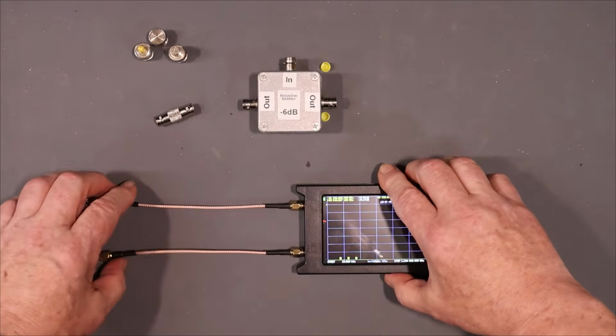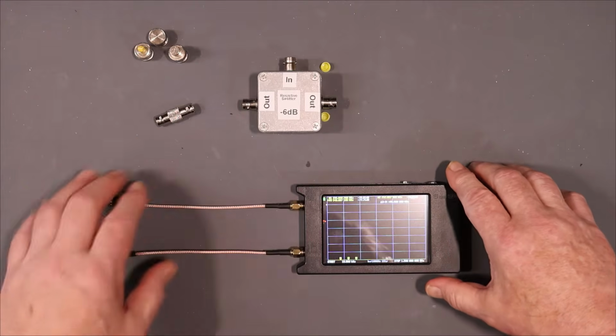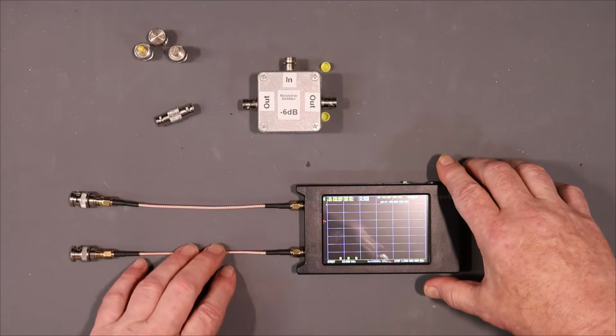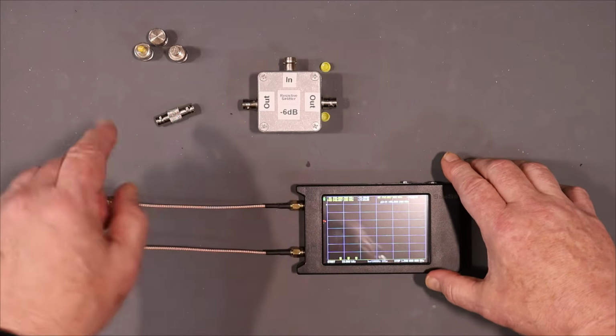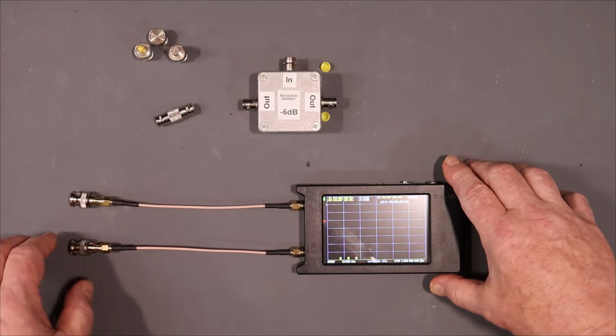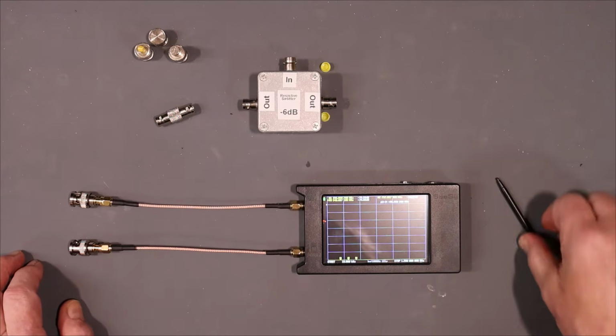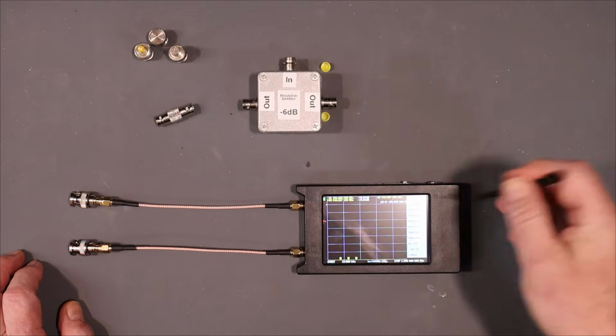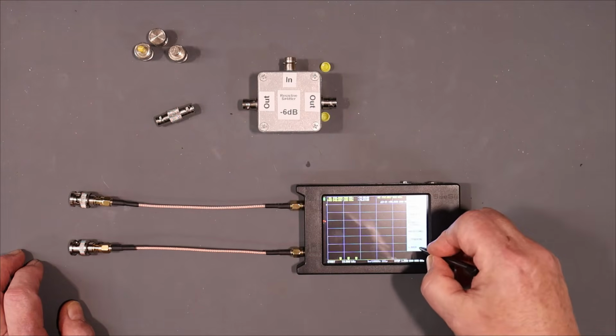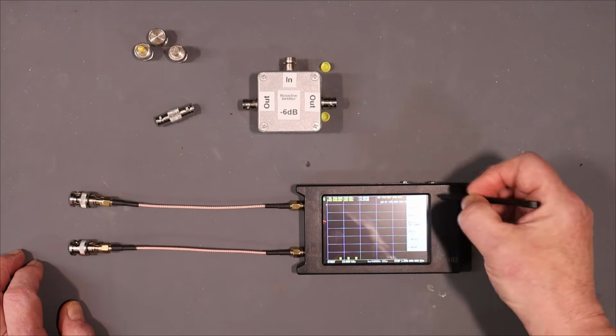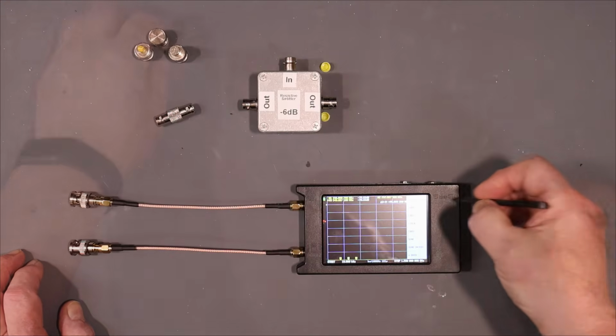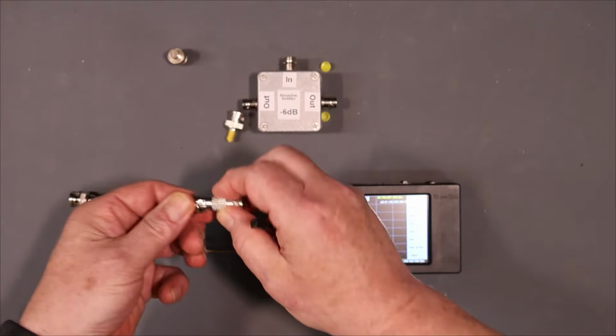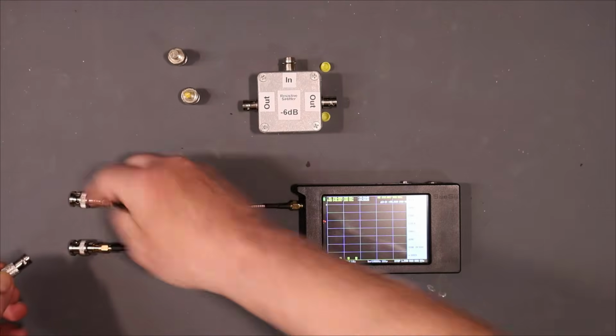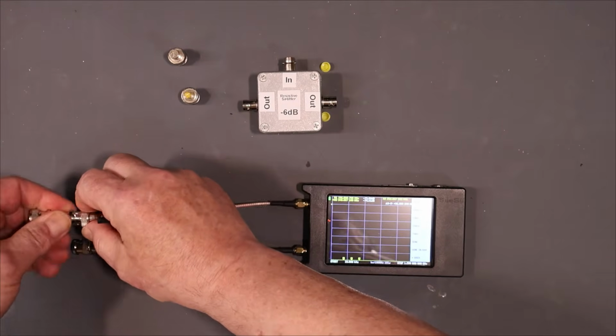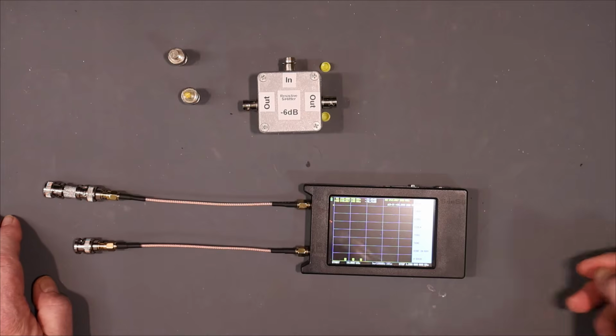Now all the calibrations need to be done on port 1 except for the through calibration, which goes through down to port 2 here. So let's start off here. We've got to do the calibrations in the right sequence. We go to calibrate, and we go to calibrate. First of all, we're going to use this because the gender of all my standards is the same gender as the cable here, so we'll use the through standard to connect all the other standards.